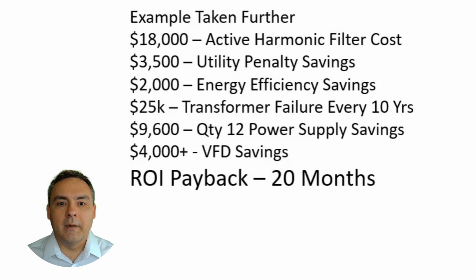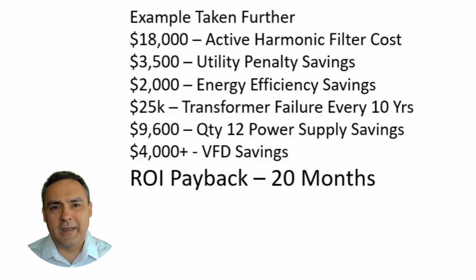So let's say that we actually install this filter for $18,000. We avoid $3,500 per year in penalties. We save $2,000 a year in energy. We prevent a $25,000 transformer failure every 10 years. We extend the life of a dozen $800 power supplies and a few $4,000 drives. The ROI payback period for this example could easily be just 20 months.